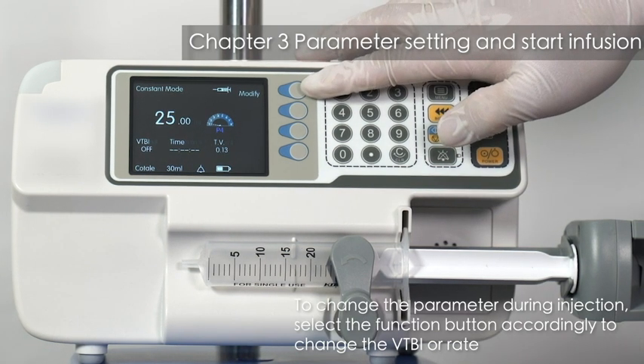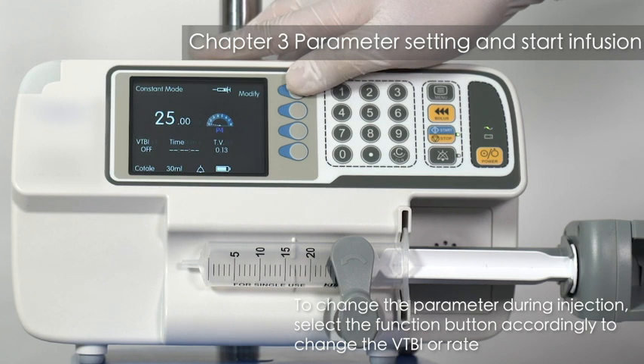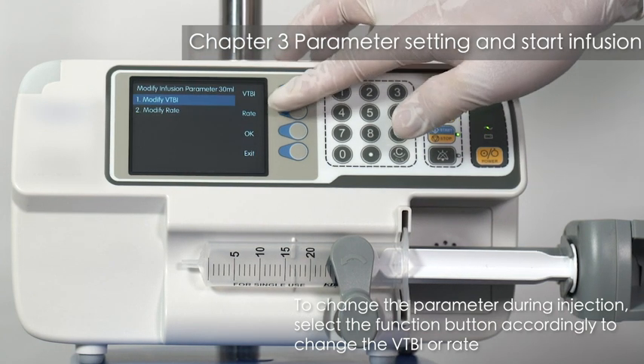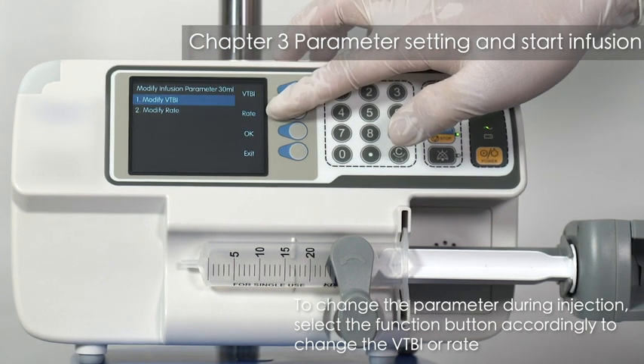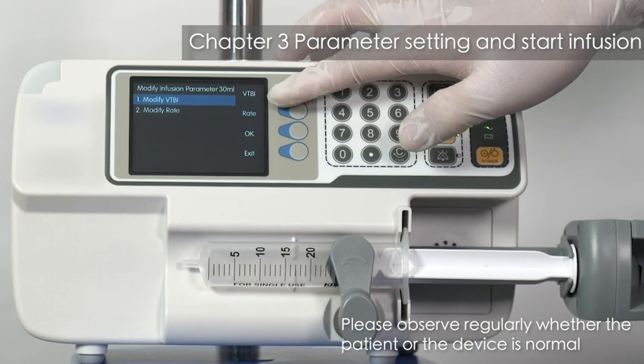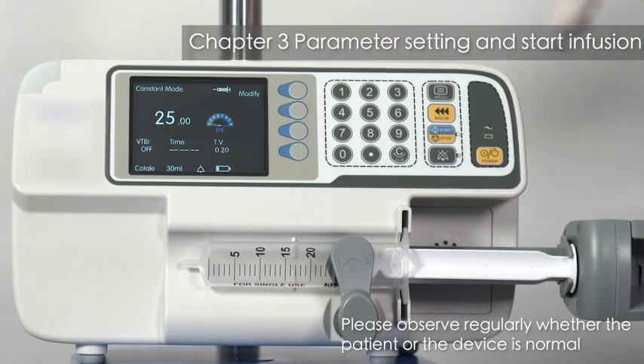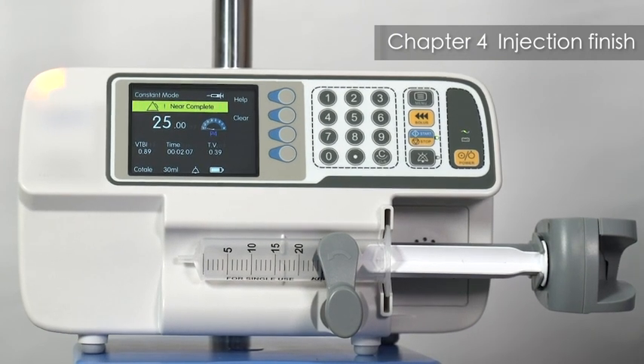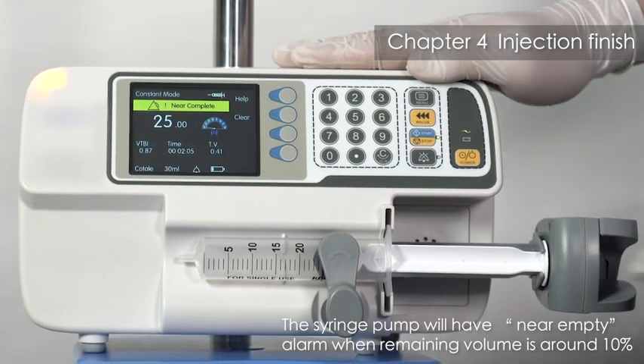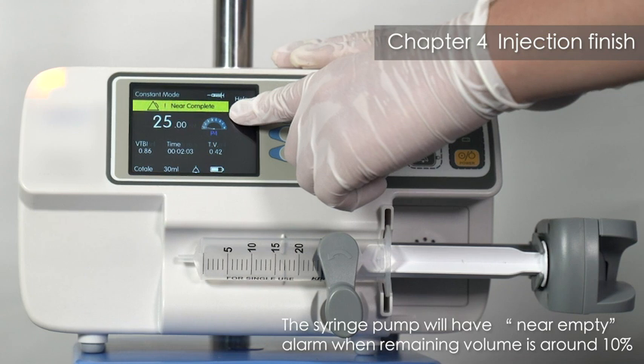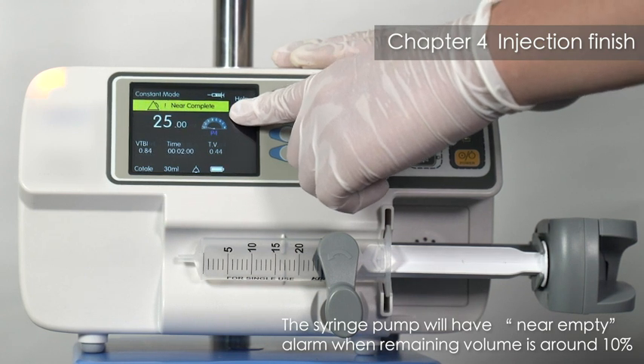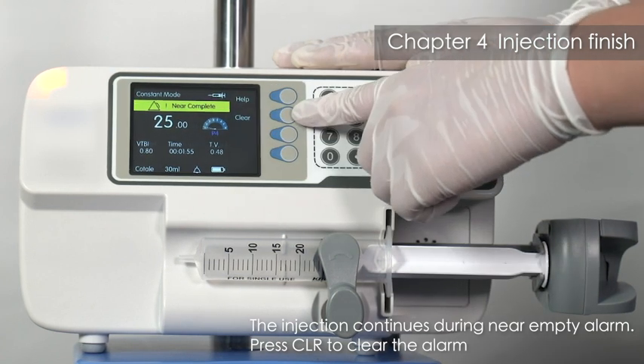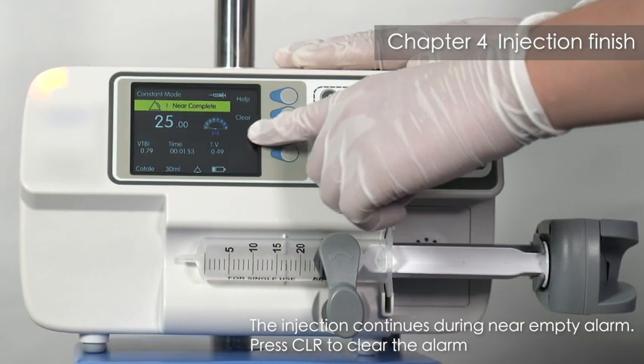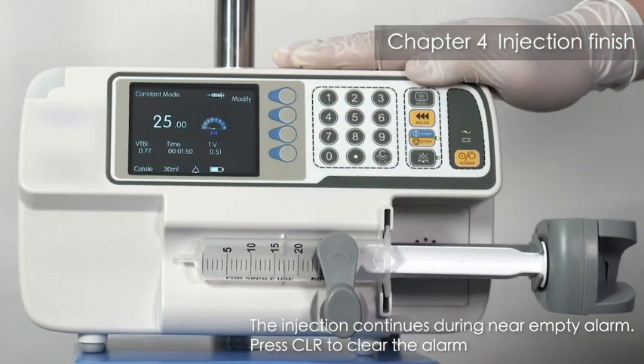To change the parameter during injection, select the function button accordingly to change the VTBI or rate. Please observe regularly whether the patient or the device is normal. Chapter 4. Injection Finish. The syringe pump will have near empty alarm when remaining volume is around 10%. The injection continues during near empty alarm. Press Clear to clear the alarm.